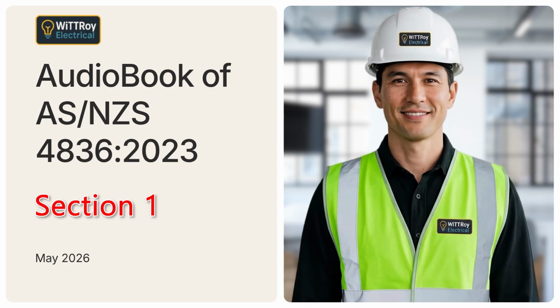Clause 1.4.29. On or near. On or near means close to exposed energized conductors or live conductive parts. The phrase does not apply in the same way if the energized part is safely shielded, segregated, barricaded, or covered with suitable insulating material so accidental contact is prevented. It can also include work that may make conductors or conductive parts become exposed and energized.